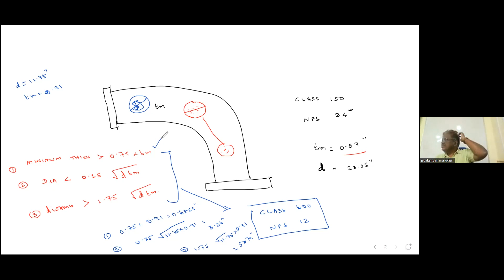We can consider this only for circular, right? No, it is not circular. Any thickness reduction, corrosion only. It is not for linear indications. Suppose there is a locally corroded area like this, one area is corroded. So you have to make a circle of the corroded area, then find the diameter of the circle. That's all. If it is not local, if it is lengthy, elongated indications, scratches or thickness reduction, it should not follow this rule. If it is a length scratch, it is not allowed.